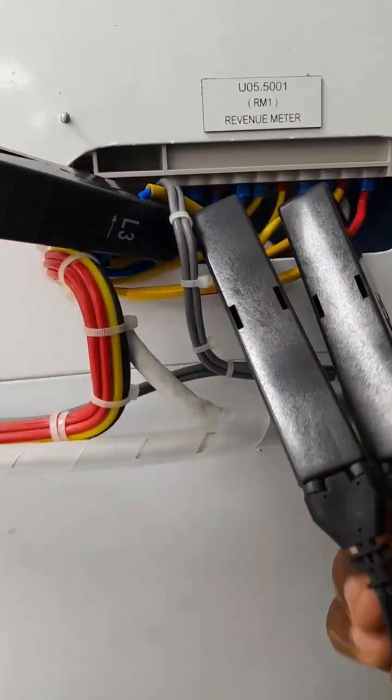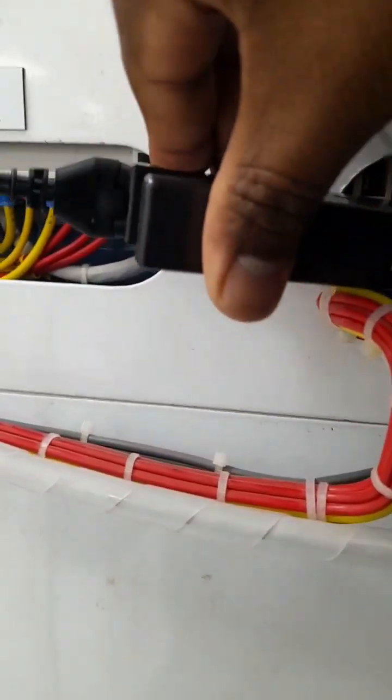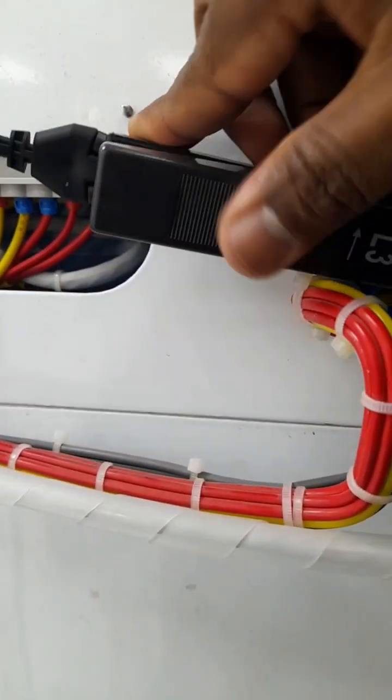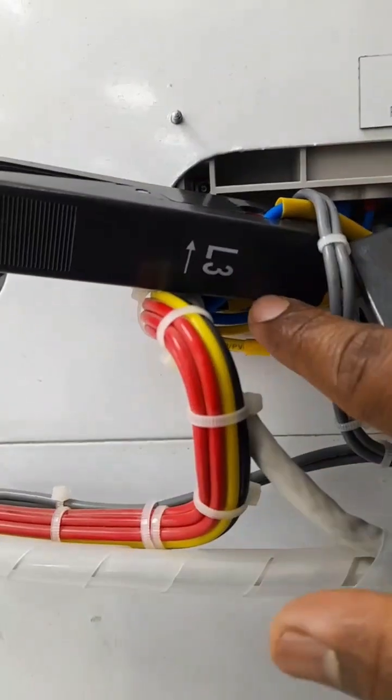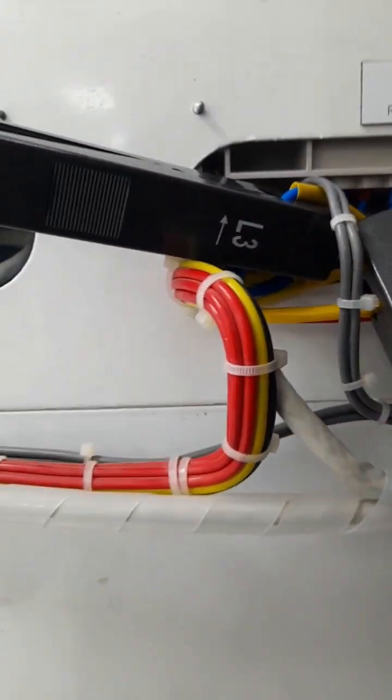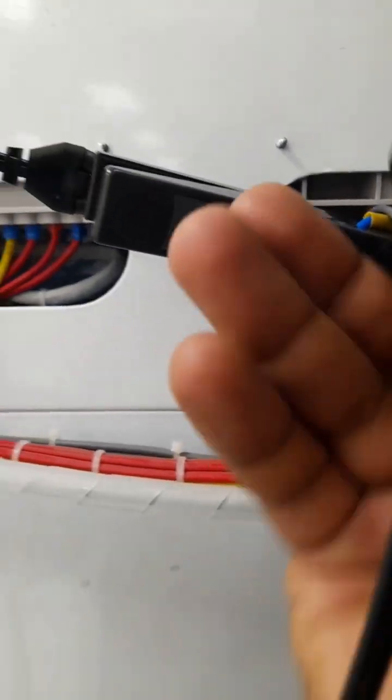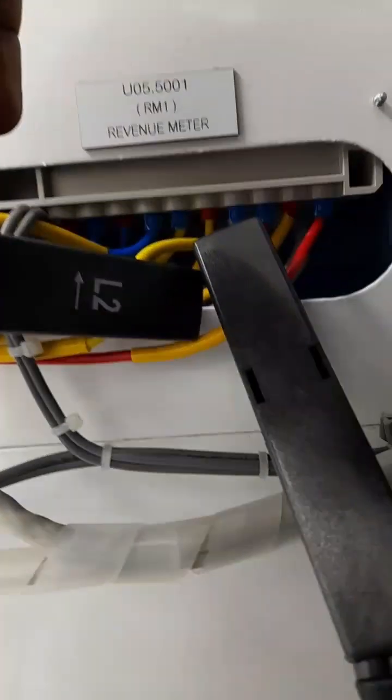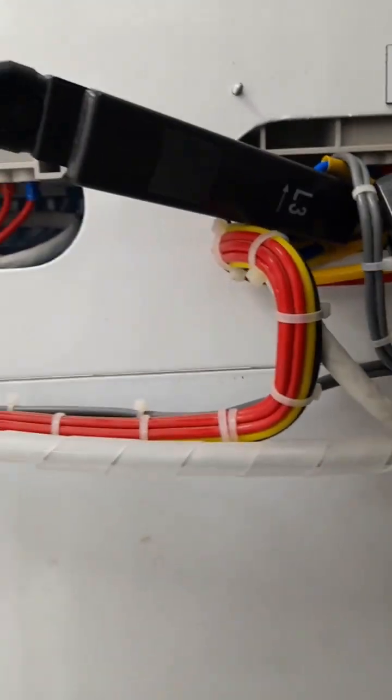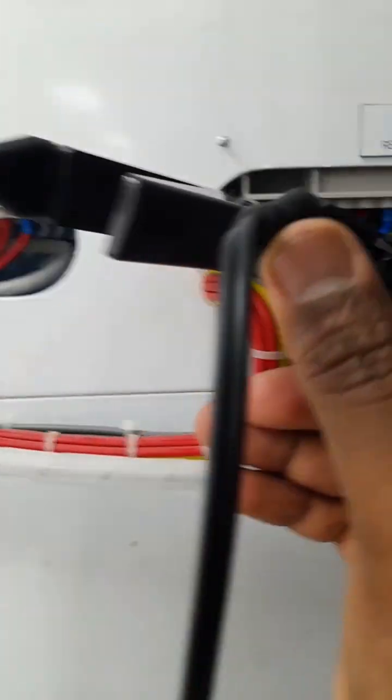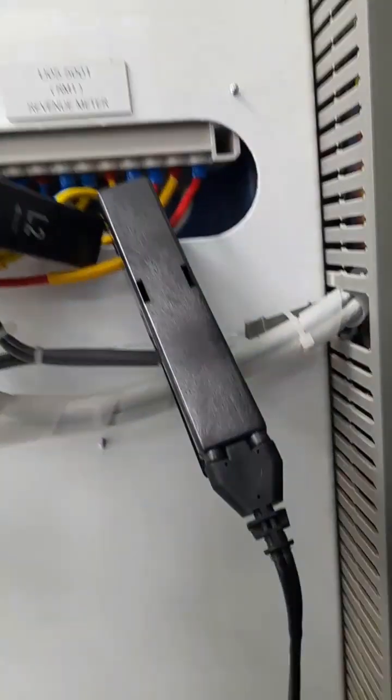The important thing is the CT clamp. When we connect this clamp, this arrow should be towards the meter. If it is in the opposite direction, it will make a huge impact on the reading. To avoid this, we have to ensure this is very important.